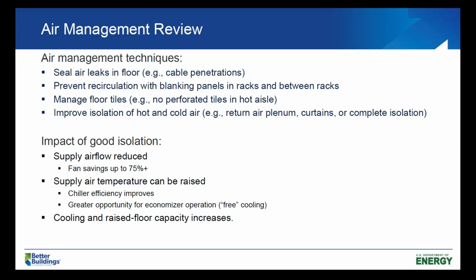All right, so reviewing again, various techniques. Sealing air leaks in the floor, like cable penetrations, preventing recirculation with blanking panels in the racks and blanking off any space between the racks, under and above the racks, as well as managing the floor tiles, especially no perforated tiles in the hot aisles, and then otherwise improving the isolation of the hot and cold air with plenums, strip curtains, or complete isolation, doors at the ends of the aisles, and so forth.